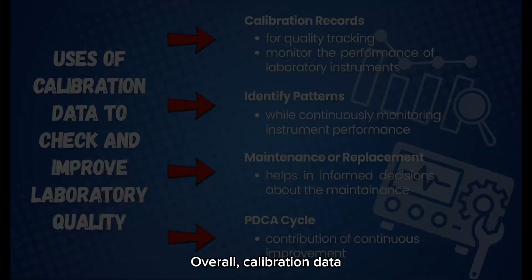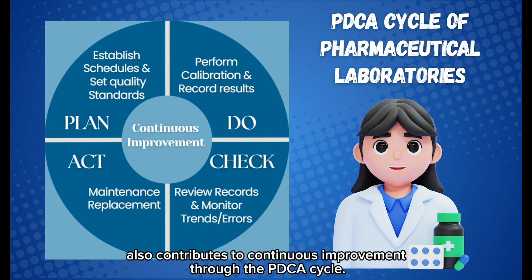Next, we focus on the use of calibration data to improve laboratory quality. Calibration records help laboratories monitor instrument performance, identify trends, and detect potential issues early. They also support decisions on instrument maintenance or replacement. Overall, calibration data also contributes to continuous improvement through the PDCA cycle. In conclusion, instrument calibration is essential to ensure accuracy, reliability, continuous improvement, and patient safety in pharmaceutical quality control laboratories.